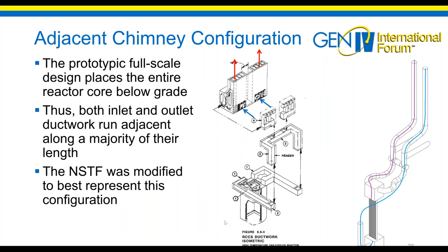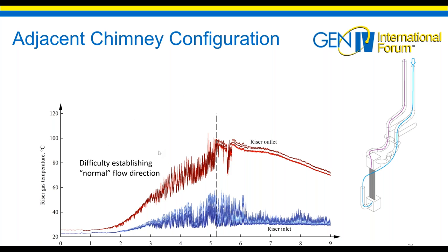Another thing we did was look at the effect of an adjacent chimney configuration, since in some design aspects the inlet and exhaust ducts were pretty close together, so we did testing to look at that. If you look at the left view graph, this gives you an idea of how we set the system up. The blue line shows the inlet that was used to the RCCS—basically we closed a valve here, ran some ductwork down to the inlet of the system, used that as the inlet, and then discharged through the normal pathway for the apparatus.